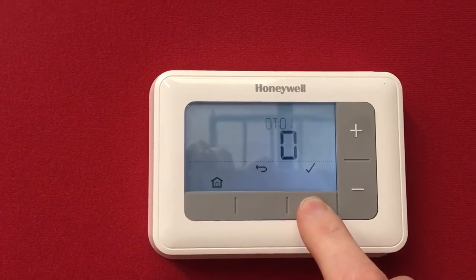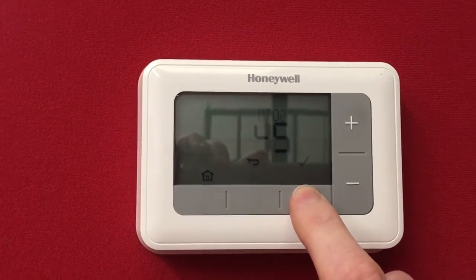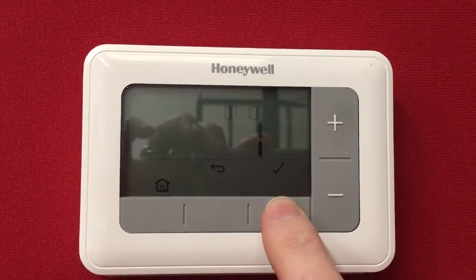So then you want to go down to OT 10. You want to go all the way down to open therm setting 10. This is where you turn outside temperature compensation on and off. So currently I've got OT 10 to 1, which is the use of outside temperature compensation.